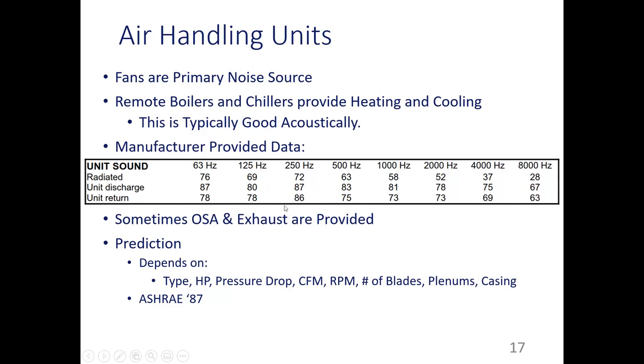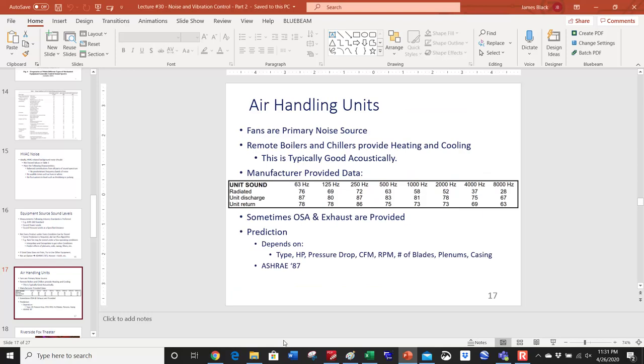Take out whatever attenuation you would get from the duct work. And then there's other stuff too. We don't know all this yet. We'll cover this later, but just account for all that attenuation and then calculate the sound pressure level at a distance. So the prediction talked about that, like you get the bare fan from the ASHRAE 87. And if you don't know, then you send half of it towards the supply and half of it towards the return. If you do know that there's an elbow in there, you can use some of the stuff we're going to learn soon to account for that. But let me show you this ASHRAE 87 calculation and some of this stuff, how that plays into it.